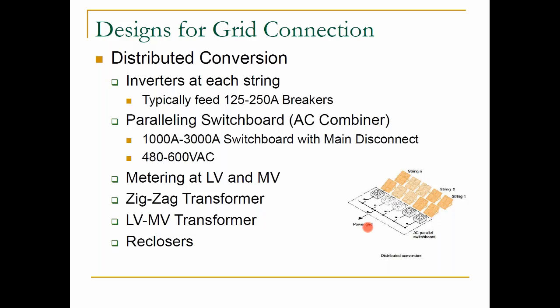John, I think you've even seen some where they're doing a little bit different installation with that. Yeah, they want a recloser, but they don't want poles on the site, so they end up using a pad mounted recloser. Yep, and it's at this point common to sometimes see the protection for the connection even up at the recloser level, correct? That's correct.